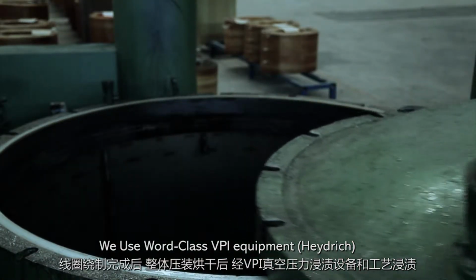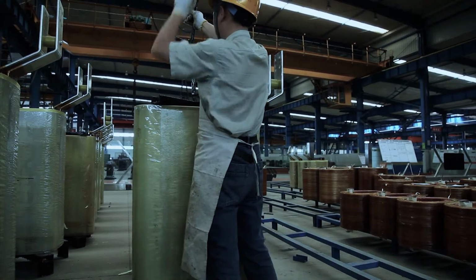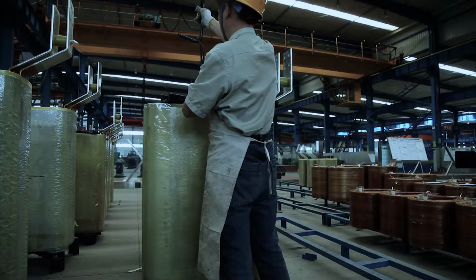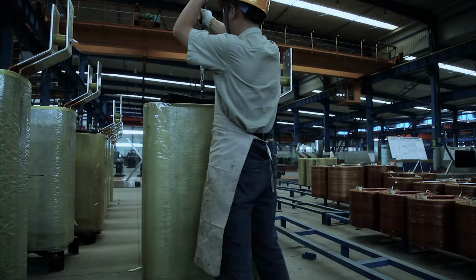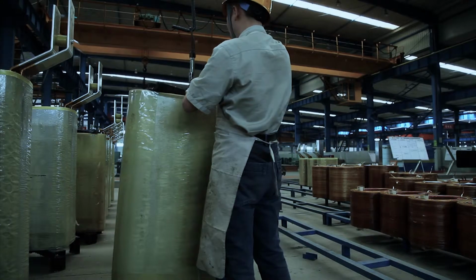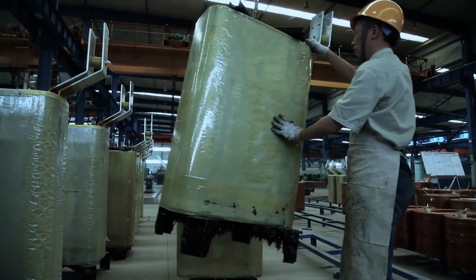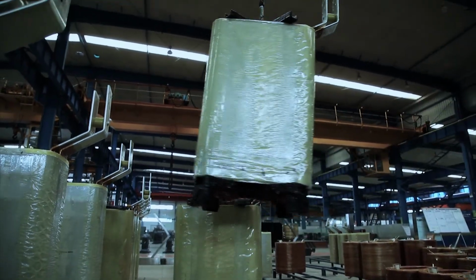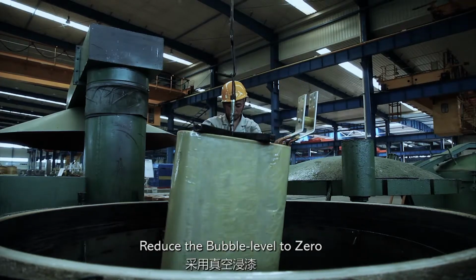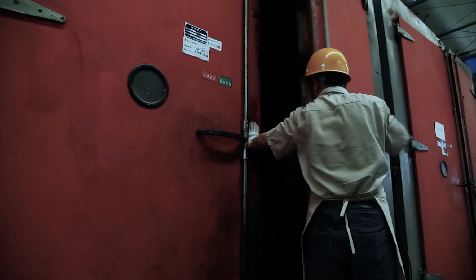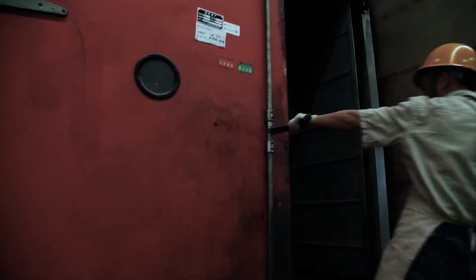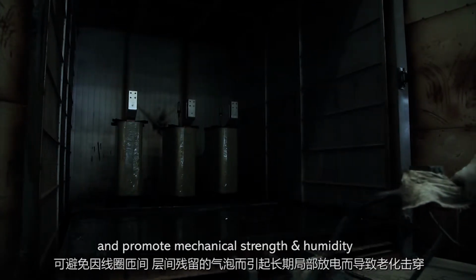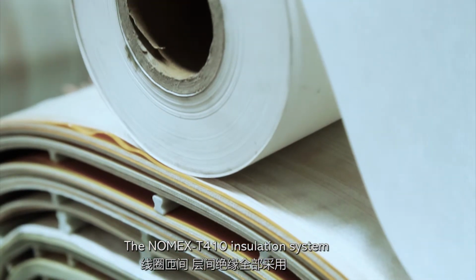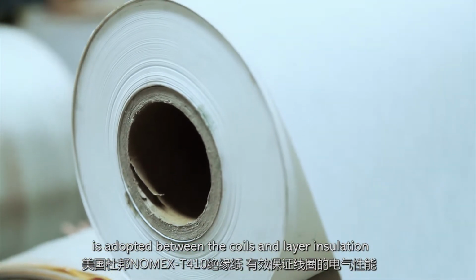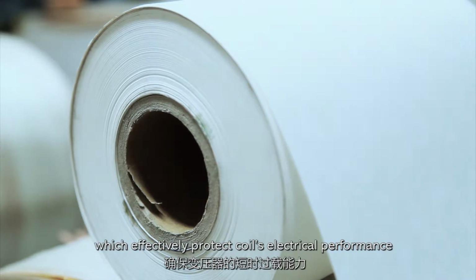We use world-class VPI equipment, Heydrich, to achieve H-class insulation, reduce the bubble level to 0, and promote the mechanical strength and humidity resistance level of the core. The Nomex T410 insulation system is adopted between the coils and for layer insulation, which effectively protects the coil's electrical performance.